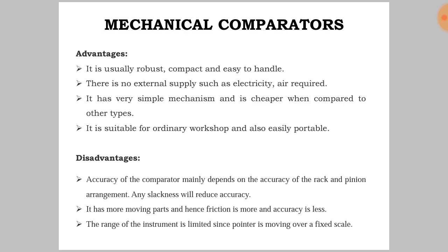Disadvantages: The accuracy of the comparator mainly depends on the accuracy of the rack and pinion arrangement, and any slackness will reduce accuracy. It has more moving parts, and hence friction is more and accuracy is less. The range of the instrument is limited since the pointer is moving over a fixed scale.